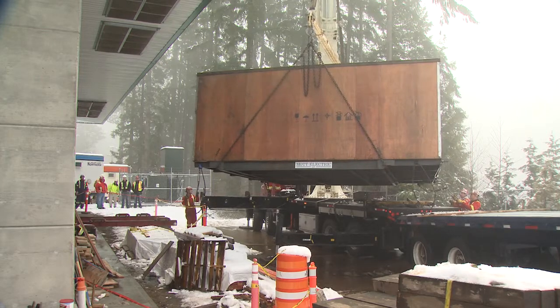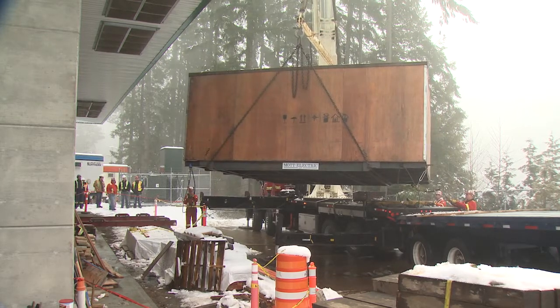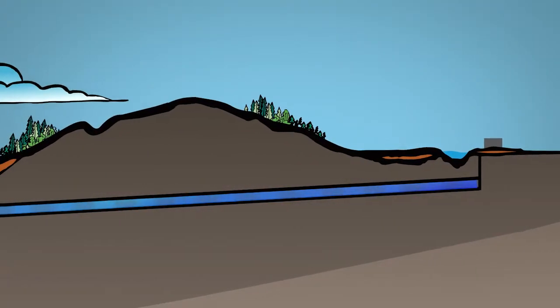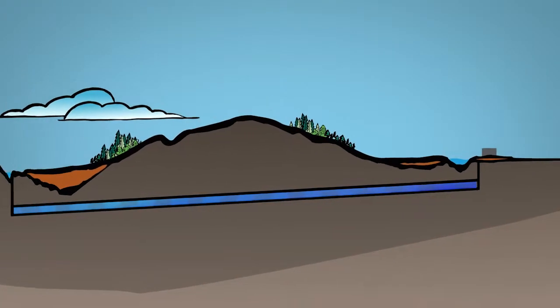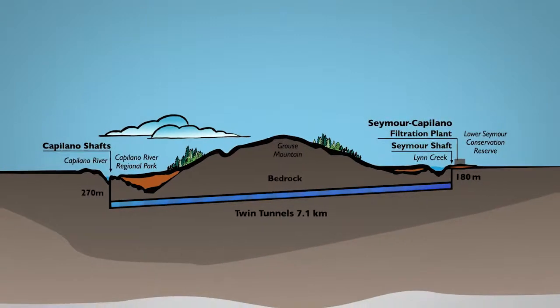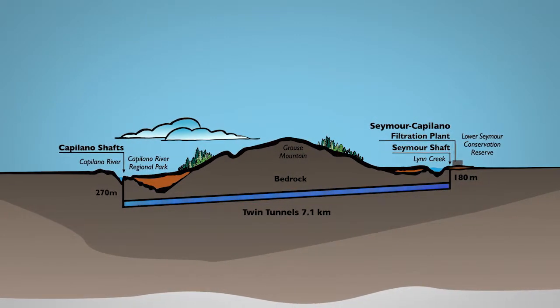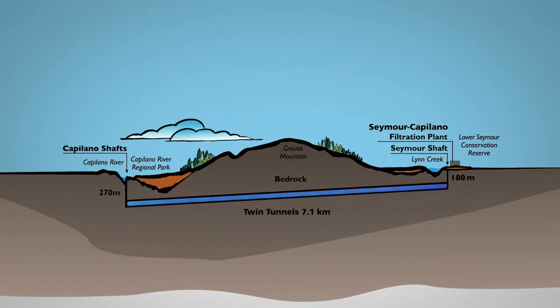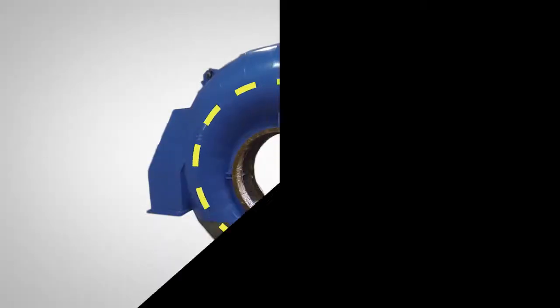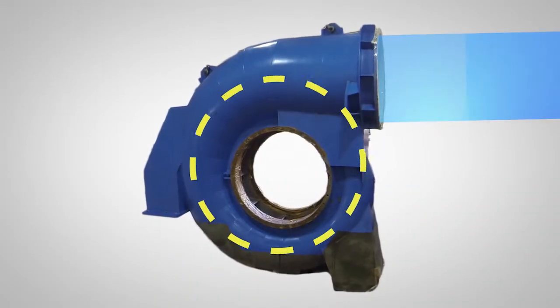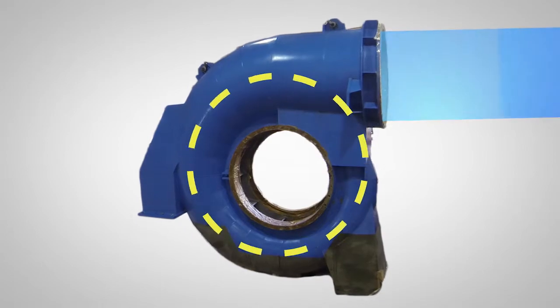The turbine is being installed as part of Metro Vancouver's Seymour Capilano water utility project, providing cost savings by harvesting the energy available from the water returning to the Capilano Reservoir from the Seymour Capilano Filtration Plant. Because the Filtration Plant is higher in elevation than the Capilano Reservoir, excess pressure will be generated when treated water is returned to Capilano for distribution. This water pressure will spin the turbine, generating electricity that can partially offset the power requirements of the pump station.